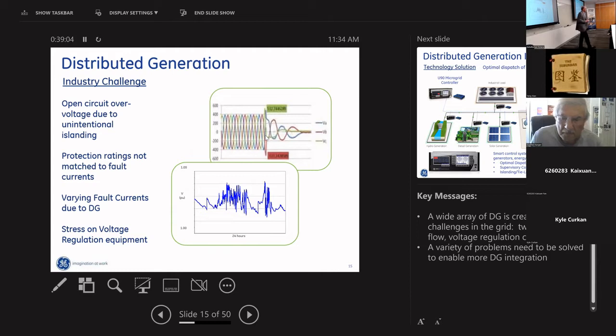Protection ratings today don't match fault currents. When I was going to set the protective relays, the first thing I did was a short circuit study. When I do the short circuit study, I typically only look at the source side contribution to the fault. I didn't consider the load side, because for years we didn't have a significant load side on distribution. Now, when you have a high penetration of distributed generation, you could have a significant load side contribution to the fault. We didn't take that into account with our short circuit study. So our protection ratings don't match our fault currents.